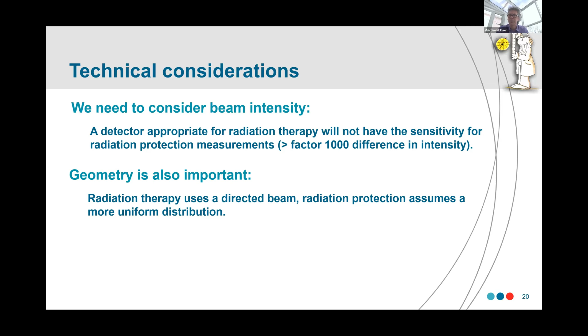So that's an example. In terms of the technical considerations beyond those system things, we have to consider beam intensity. So we have detectors appropriate, say, for radiation therapy, that will not have the sensitivity required for radiation protection. So when we're looking at alternatives, we have to ask the question of what is the beam intensity, what is available, and is that appropriate for calibration? And then how do we go from that to an end application? Geometry is also important. Radiation therapy uses a directed beam. Radiation protection assumes something more uniform or a much wider field. A source intended for one may not be applicable to another. We have to consider this.